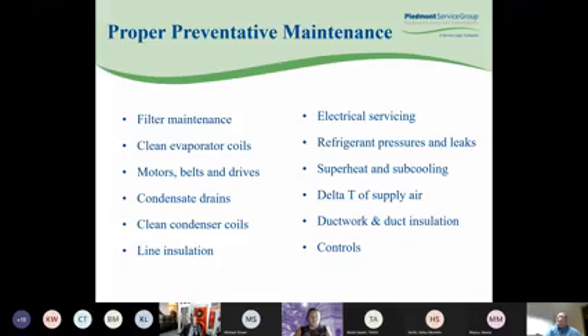So what should our maintenance be? We should do filter maintenance, wash evaporator coils, check our motors, belts, and drives, condensate drains, clean condenser coils, line insulation, electrical service, and refrigerant pressures and leaks, superheat, subcooling, delta T of supply air, ductwork, and duct insulation, and controls. Setting up the PM schedule should follow your O&M manuals. Scheduling should also take into consideration the environment.